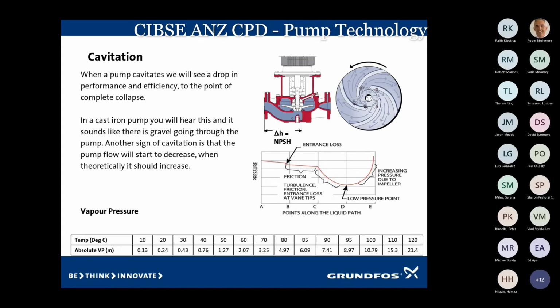When the water is leading up slightly into the impeller vane, it's just starting to move up into the vane. Some of that vapor and water mixture is starting to create some pressure. So as it climbs up the impeller vane, that mixture condenses back down to water. And so that passage between D and E is where the cavitation is happening.